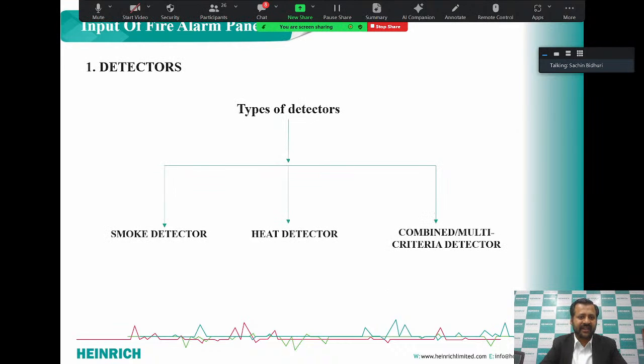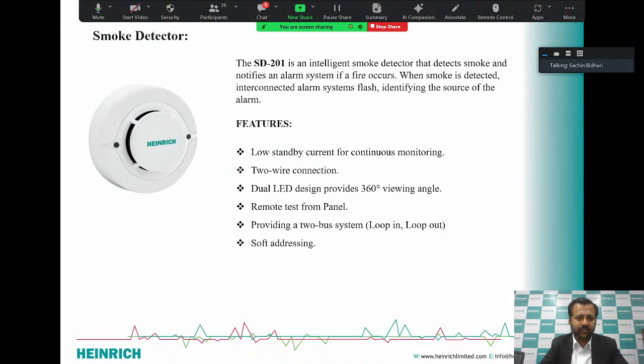Detectors: there are basically different types of detectors. One is smoke detectors, heat detectors, multi-criteria detectors. Then we have duct detectors and beam detectors. We provide all these types of detectors under the make of Heinrich. This one is the smoke detector. Even the part codes are mentioned on all the slides. This is SD201, the smoke detector, and it has a very low standby current for continuous monitoring. It is connected in the loop. So this is the smoke detector that we have.